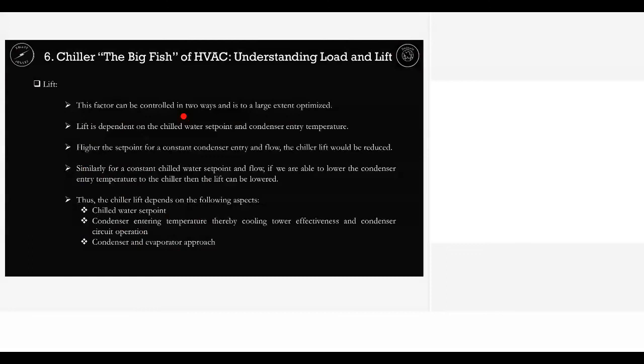The second aspect is the chilled water outlet or chiller set point. Imagine my set point is 5 degrees Celsius in the daytime, when the outside is really hot, my building has a lot of people and a lot of equipment running, so I need to make it really cold because of the very large internal load. But in the evening and at night, when the load is less, when people are fewer, when the OPD shuts down, when the outside temperature is falling, then I don't need 5 degree water. I can come up to 7, 8, 9 or 10 degrees. That means the temperature of the evaporator is coming up and the pressure is coming up. The temperature of the condenser is coming down and the pressure is coming down. That means the effective lift is coming down. That is what is written here. So that is actually about lift.